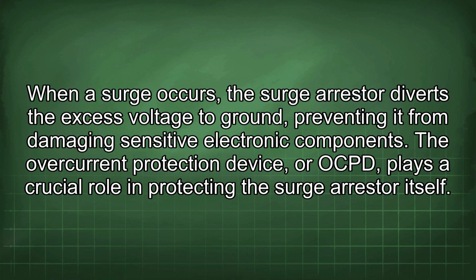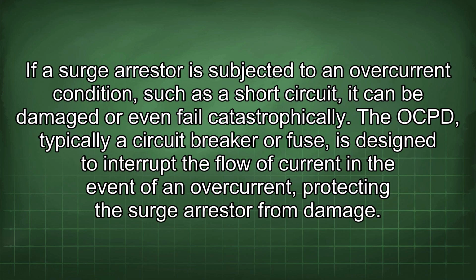damaging sensitive electronic components. The overcurrent protection device, or OCPD, plays a crucial role in protecting the surge arrestor itself. If a surge arrestor is subjected to an overcurrent condition, such as a short circuit, it can be damaged or even fail catastrophically. The OCPD, typically a circuit breaker or fuse, is designed to interrupt the flow of current in the event of an overcurrent, protecting the surge arrestor from damage.